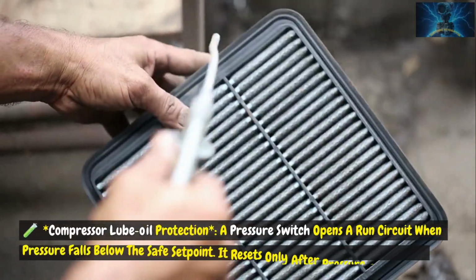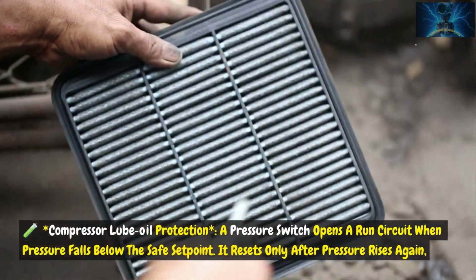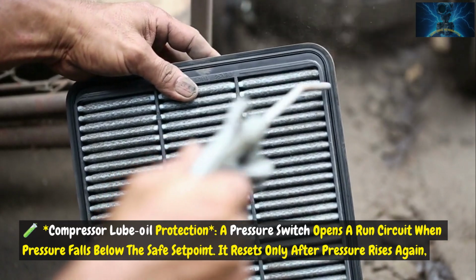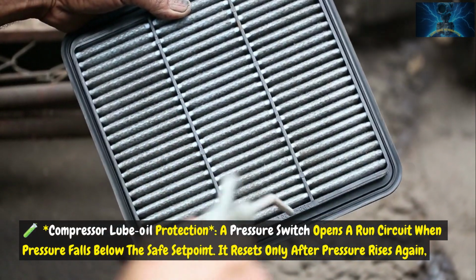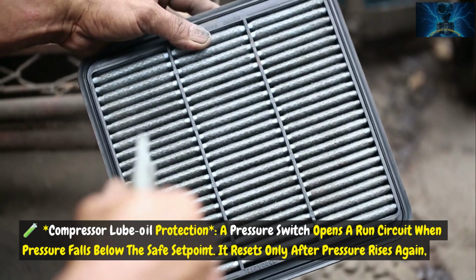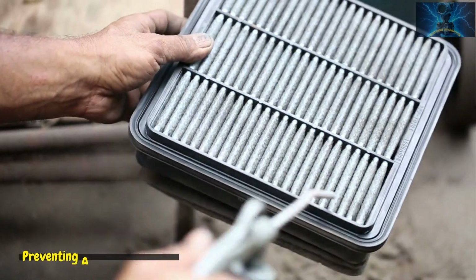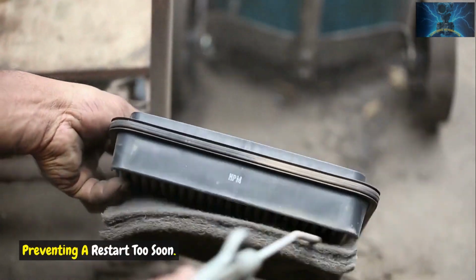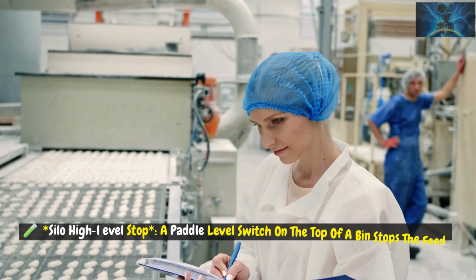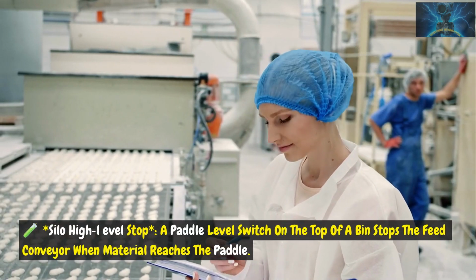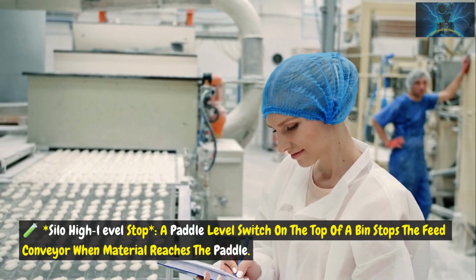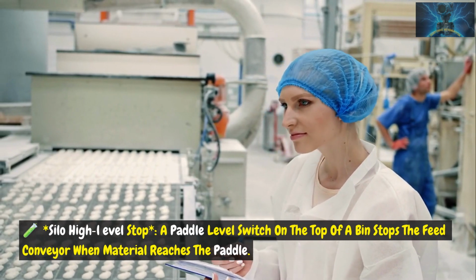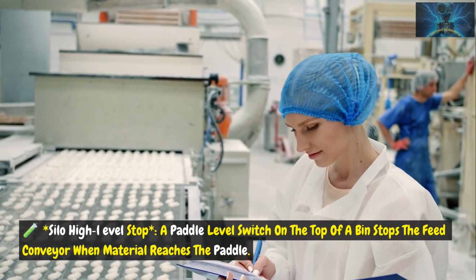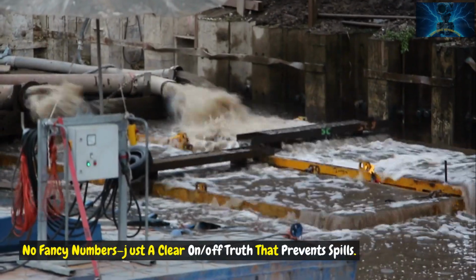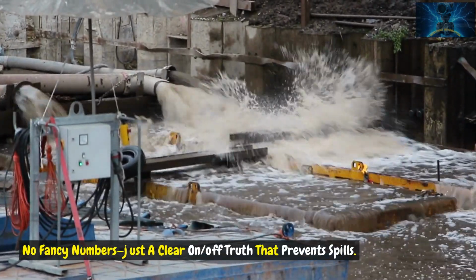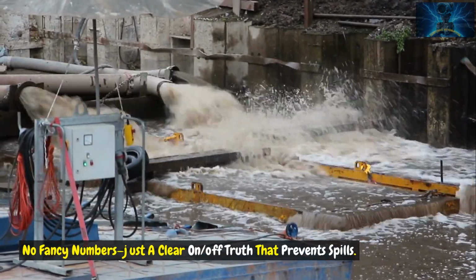Compressor lube oil protection. A pressure switch opens a run circuit when pressure falls below the safe set point. It resets only after pressure rises again, preventing a restart too soon. Silo high-level stop. A paddle-level switch on the top of a bin stops the feed conveyor when material reaches the paddle. No fancy numbers, just a clear on-off truth that prevents spills.